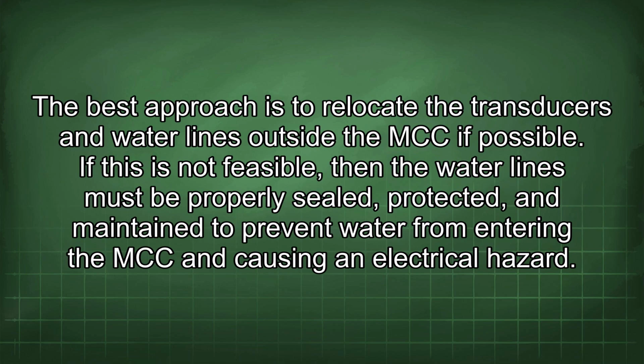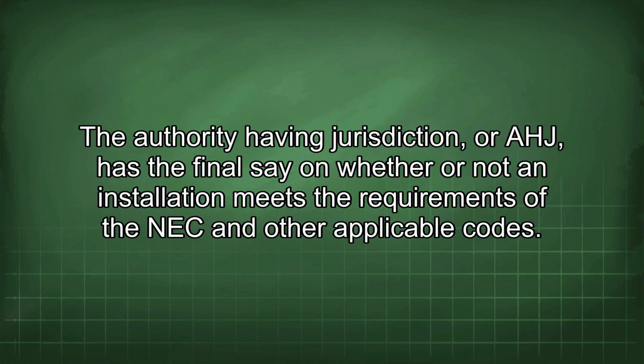The best approach is to relocate the transducers and water lines outside the MCC if possible. If this is not feasible, then the water lines must be properly sealed, protected, and maintained to prevent water from entering the MCC and causing an electrical hazard. The authority having jurisdiction, or AHJ, has the final say on whether or not an installation meets the requirements of the NEC and other applicable codes.